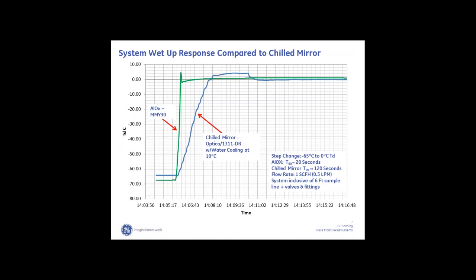These sensors have a very good wet-up response. You can think of the sensor as almost like a ceramic sponge. Just like a kitchen sponge will absorb a lot of water very quickly — a dry sponge thrown into a sink of water would suck it up almost immediately — but it takes time to dry out. The aluminum oxide has a high affinity for water and will suck it up very rapidly. Here we show a comparative graph of the response on a step change from about negative 65 to zero dew point, and that occurred in about 20 seconds at only one standard cubic foot per hour flow.